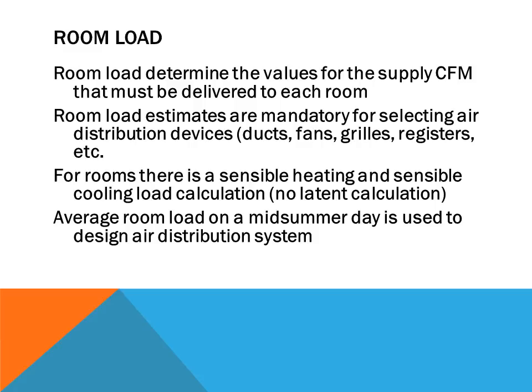Room loads determine the values of supply CFMs. Once we determine the block load, which is the whole structure, then we need to look at each separate room individually, and these individual loads for the room will determine how much air is required for these different rooms. That way we can know how to size up the ductwork. So once we determine block loads, then we will go to the individual room loads.